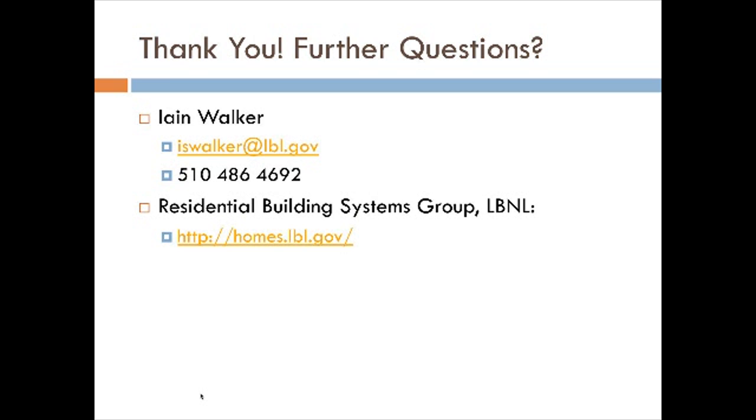There are people who are trying to bring costs down doing, say, open source stuff, so that if you're an equipment designer or specifier, you could use some of those resources. But again, they are limited by the fact that these sensors don't hold their calibration long enough, or don't work well enough for long enough for us to rely on that as controlling our ventilation system, rather than what we do now, which is this outdoor air to dilute.